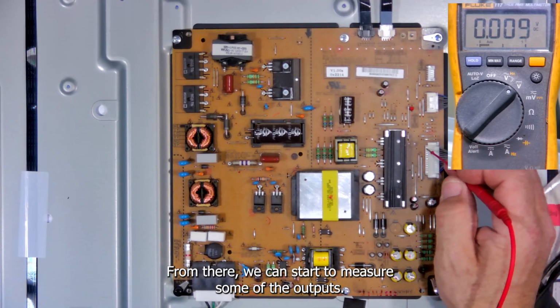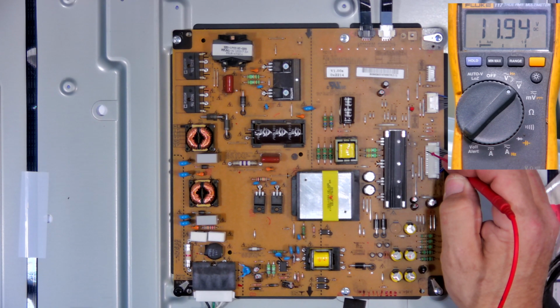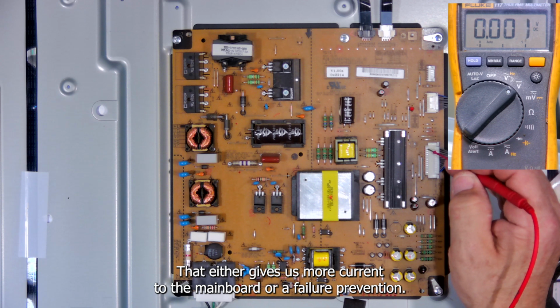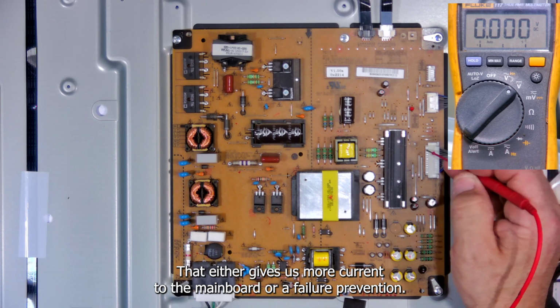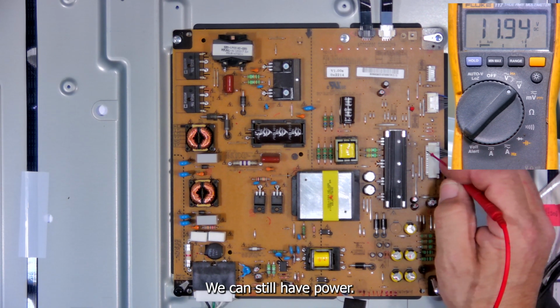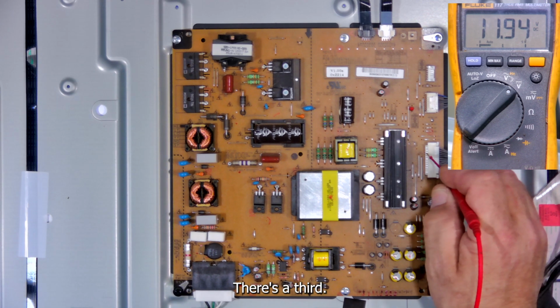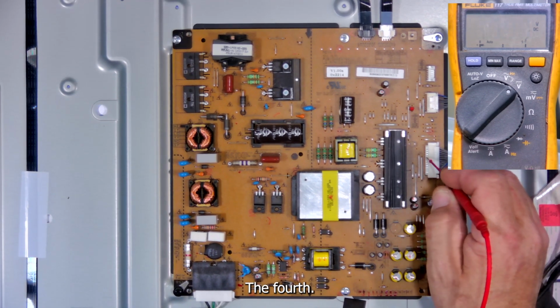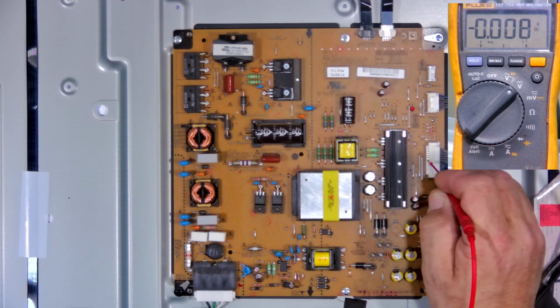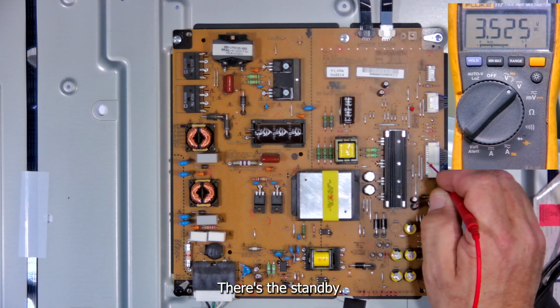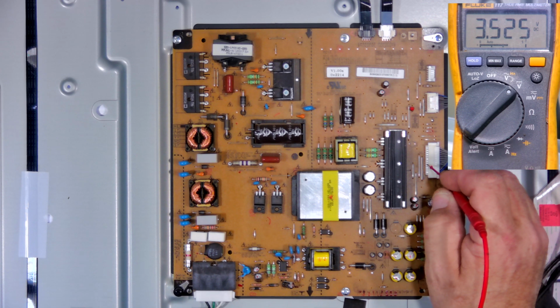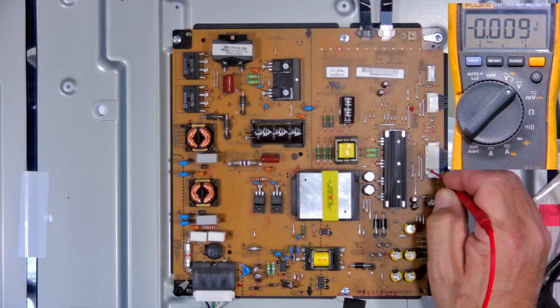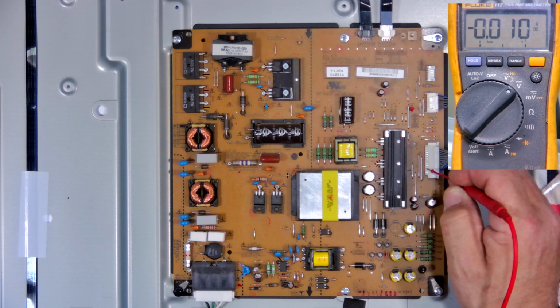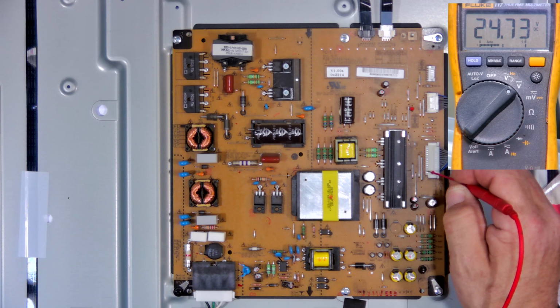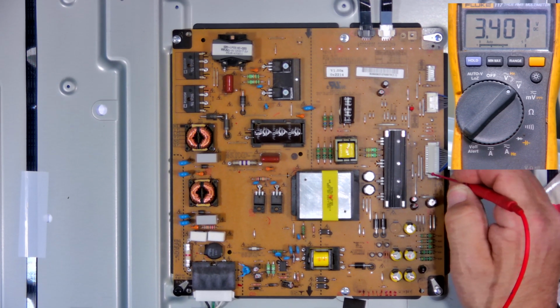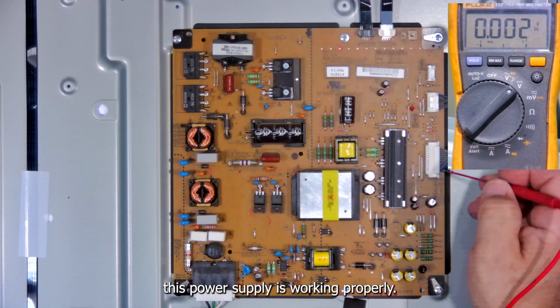From there, we can start to measure some of the outputs. That's a redundant 12 volt. That either gives us more current to the main board or a failure prevention in case one of these solders is bad. We can still have power. And there's a third. And a fourth. There's the standby. Looks like everything on this power supply is working properly.